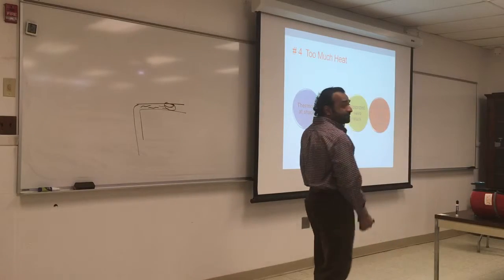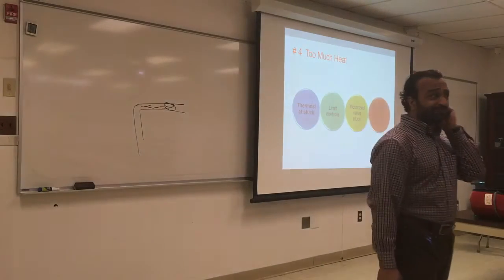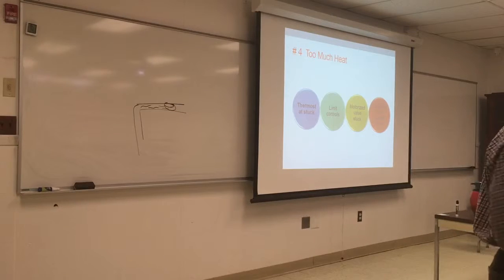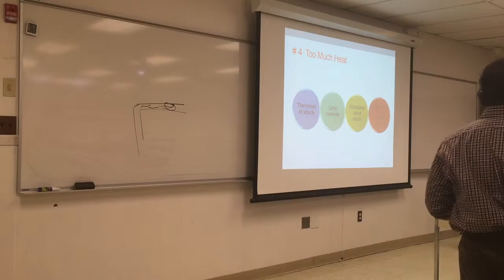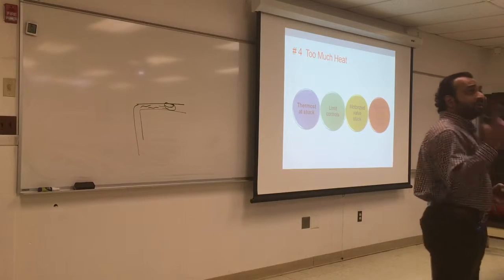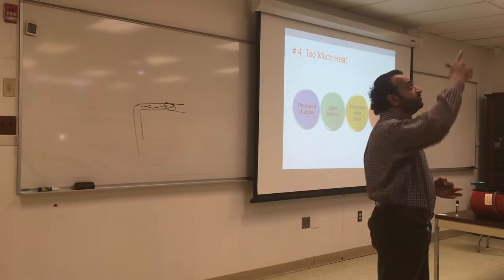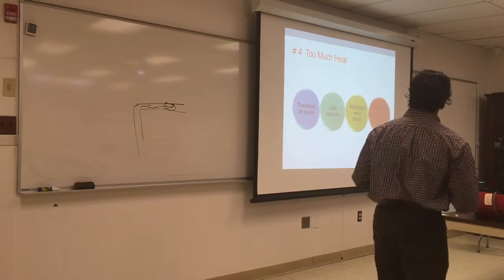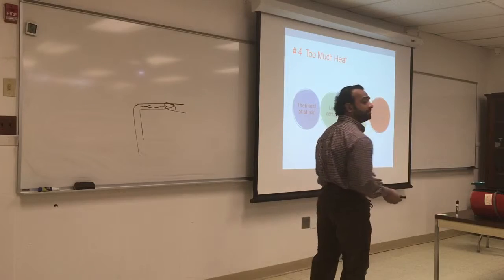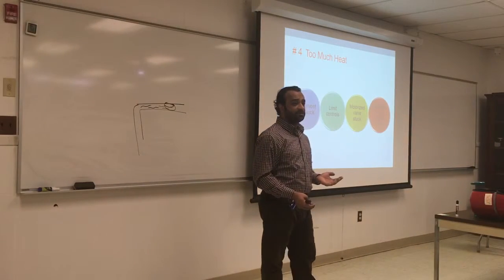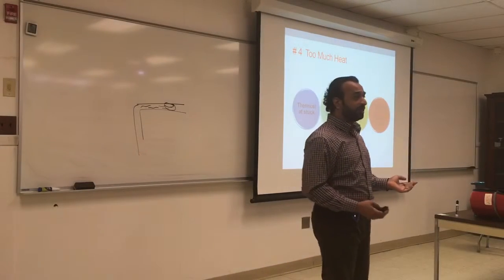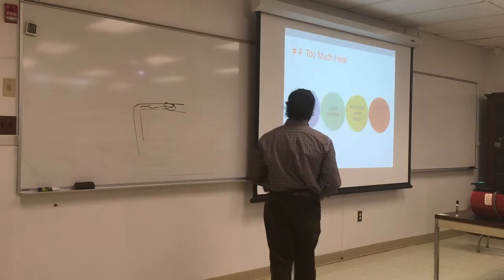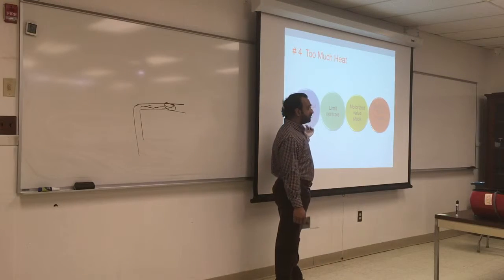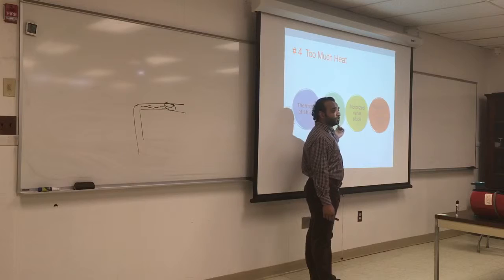Too much heat. So we had too little heat. Either the burner is not sized correctly, the radiator is not sized correctly, the radiator is blocked, the filter is clogged, or these registers are blocked by something. So that's for hot air. For steam, we do not have enough steam if the vent is venting air out of the steam system. If you have too much heat, the thermostat will be stuck or faulty, or the limit is set too high.